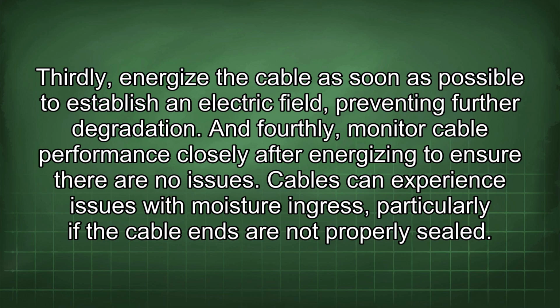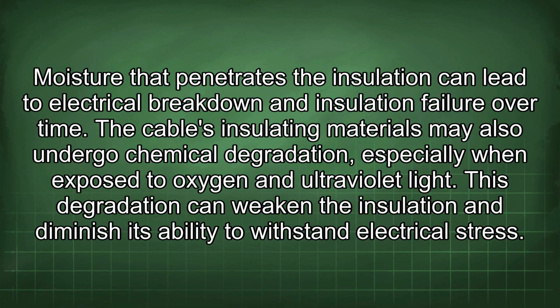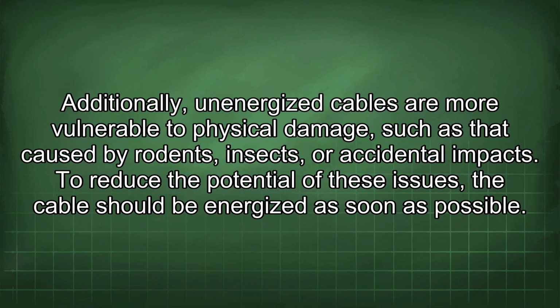Cables can experience issues with moisture ingress, particularly if the cable ends are not properly sealed. Moisture that penetrates the insulation can lead to electrical breakdown and insulation failure over time. The cable's insulating materials may also undergo chemical degradation, especially when exposed to oxygen and ultraviolet light. This degradation can weaken the insulation and diminish its ability to withstand electrical stress. Additionally, unenergized cables are more vulnerable to physical damage, such as that caused by rodents, insects, or accidental impact.